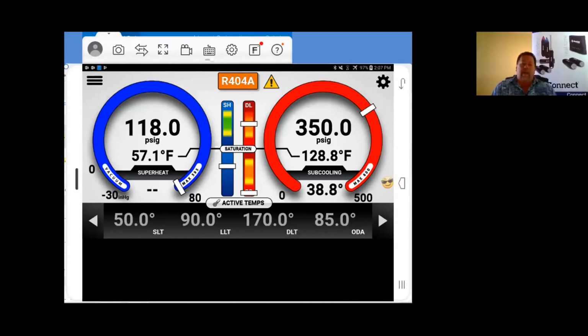So what I'm showing you right now is just simply a set of pressures, and there's actually temperatures from supply and return. Now, the issue about connecting up, when somebody's gauging up to a system, everybody has to gauge up to a system. If you're going to take temperatures, you're still going to do it the same way. The only thing additional that you do with an iManifold or an iConnect system is when you're going to attain airside measurements. And those are just simply putting one probe into your supply line and one in your return.